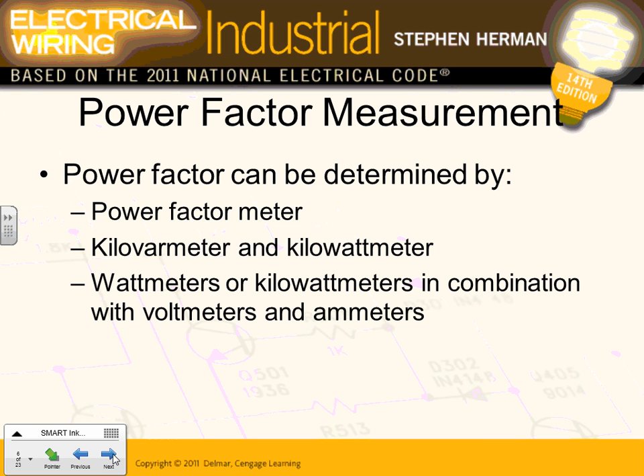Okay, power can be determined by, so we'll do the calculation later on the power triangle, but how do you calculate the power triangle? If you get into any commercial industrial building right now, the utility will get you a meter, one or two meters. If there are two meters, one will be measuring the kVAR in your building, and one will be measuring the kilowatt hour. Or one meter that can give you both readings. Based on the kVAR and the kilowatt hour, they can decide what the power factor is in your building. And if your power factor is maintained below 90 for a certain amount of time, you will get a letter from them saying you have been penalized and you have to improve your power factor. That's how they maintain it.